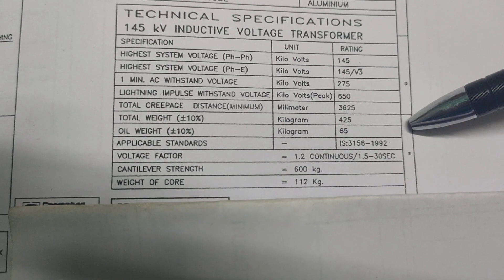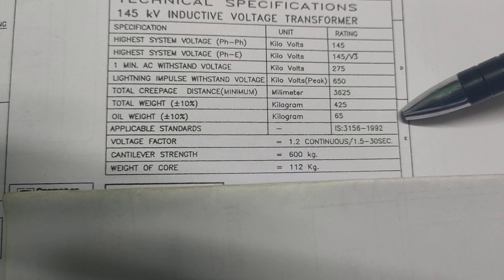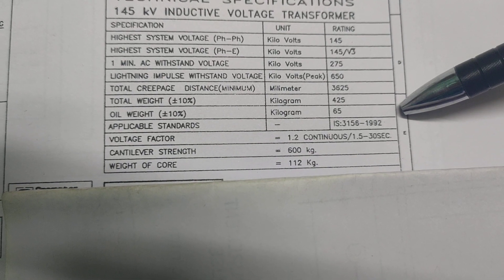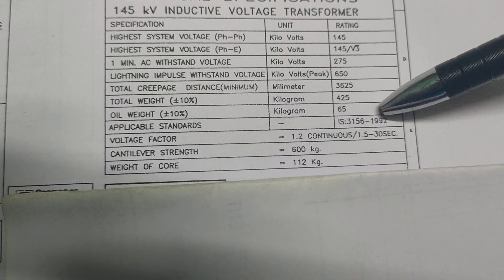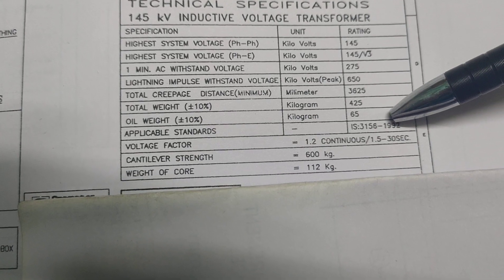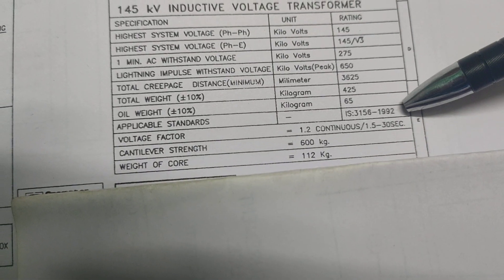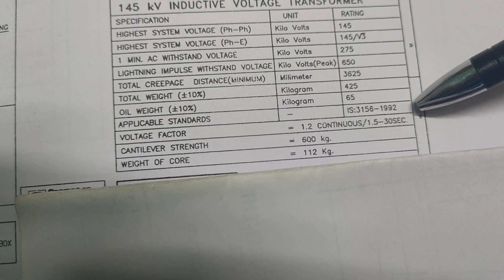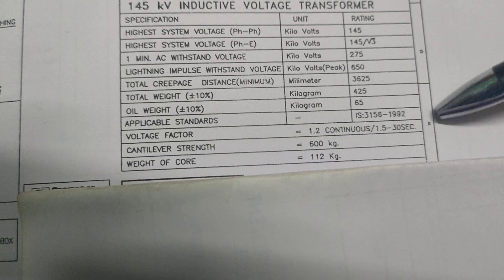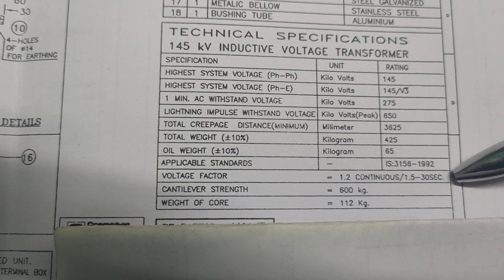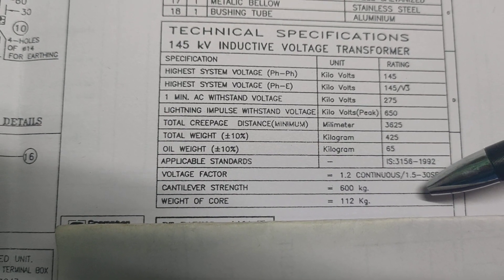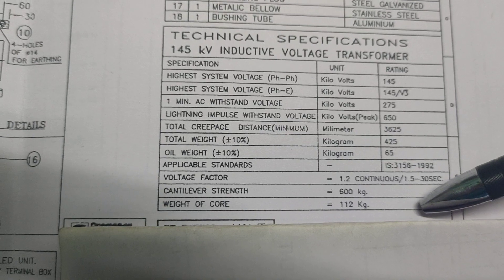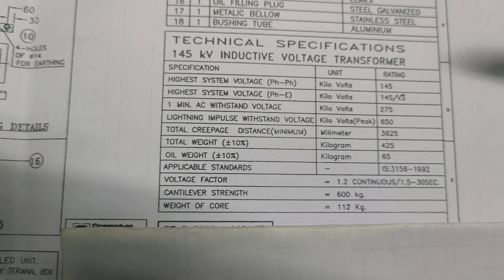Total weight is 425 kilogram. Total oil weight plus minus 10 percent is 65 kilogram. The standard maintained IS 3156 oblique 1992. The voltage factors 1.2 continuous, 1.5 for 30 seconds. Cantilever strength is 600 kg and weight of the core is 111 to 112 kg.